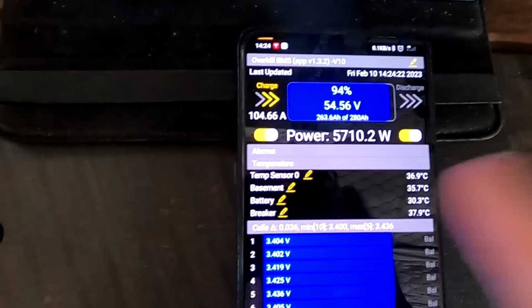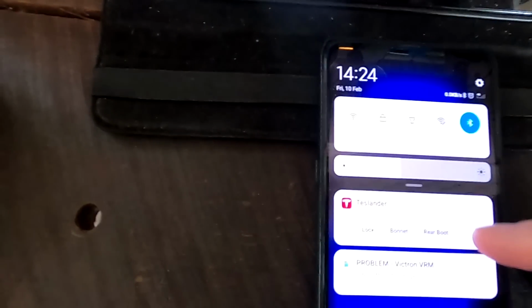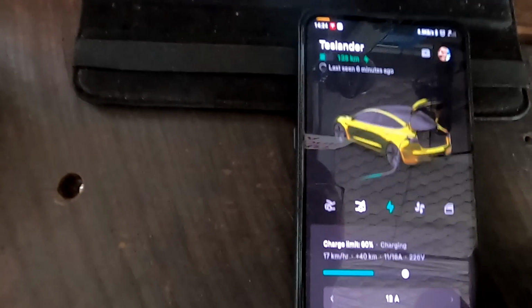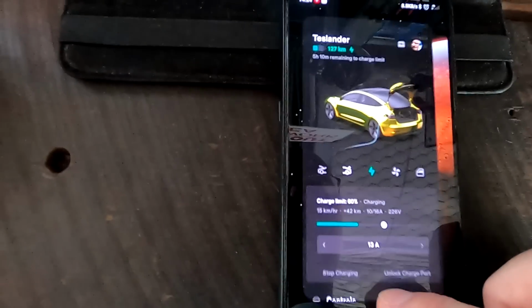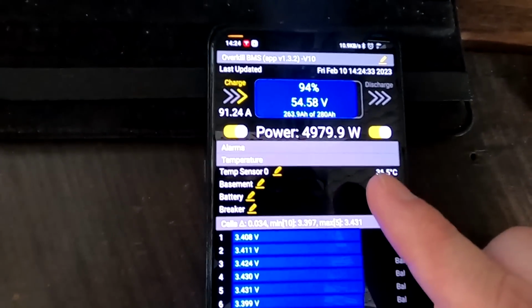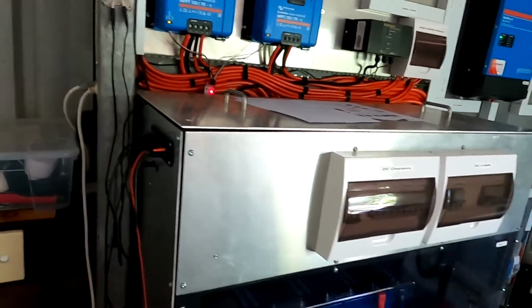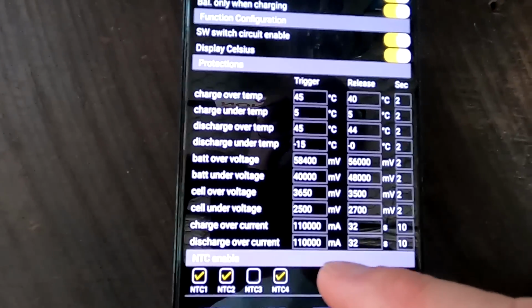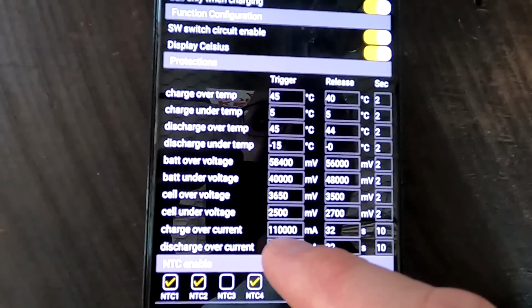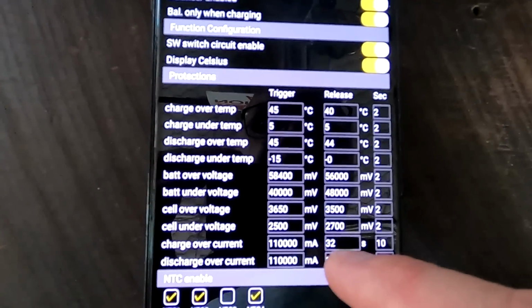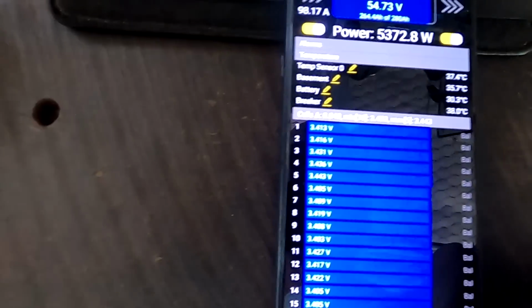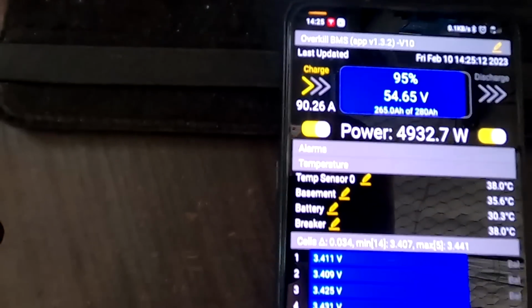We need to be mindful, this is only a 100 amp BMS here. I will probably increase the charging current here of the Tesla for a moment. I don't want to trigger this BMS here because then the whole show shuts down. I don't want to risk that. Yeah, this is only a 100 amp 48 volt BMS here from Overkill Solar. They're not making any larger one for 48 volt, unfortunately. And here in the protection section you can see the charge overcurrent is 110 amps for 10 seconds and then it turns off. So we are close to 100 amps now.